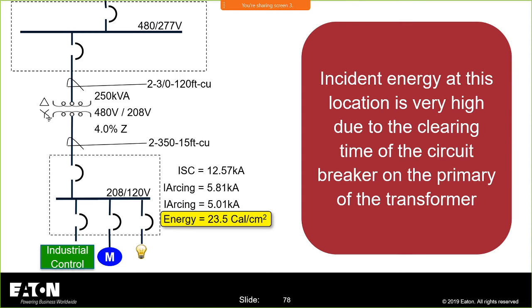Now, I'm picking it based upon the full load amps at a higher percentage, and then I'm going to size my conductor after I figure out what breaker I'm going to put in there. When I do that, the instantaneous of that circuit breaker is going to be a little bit higher than what it would be if I just sized it for the full load amps. So you combine the transformation of voltage, the through currents are going to be lower on the primary than on the secondary. I have an instantaneous on a breaker on the primary that's a little higher than what I would like. And now I have a long clearing time, and hence I'm at 23.5 calories per centimeter squared.